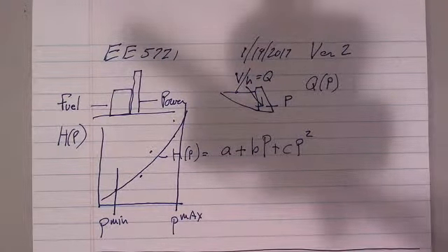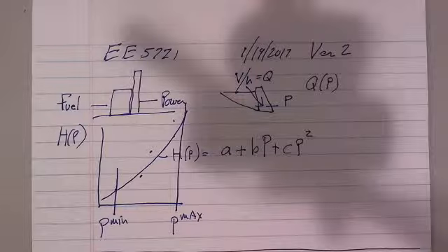For any kind of generator, the max is easy to understand: the rate at which you can deliver steam into a big steam turbine, the rate that you can deliver water to a hydro turbine, the rate that you can deliver gas into a large gas turbine, is all the mechanical end of the generator, and there's a limit, usually depending on how the thing was designed.